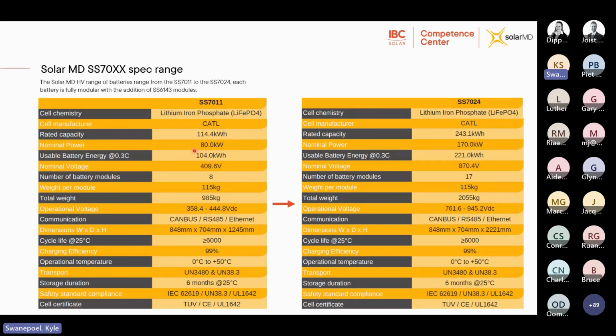So each battery module gives you 14.3 kilowatt hours of energy and gives you 10 kilowatts of power. So you can do the calculation based on the number of battery modules that you require. And each battery module is 51.2 volts. So connecting 8 of those in series will give you 409.6 volts nominal voltage.